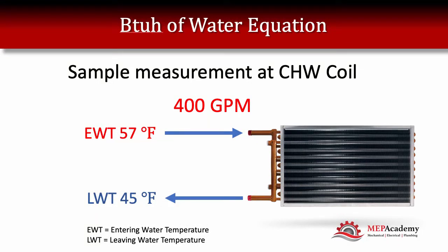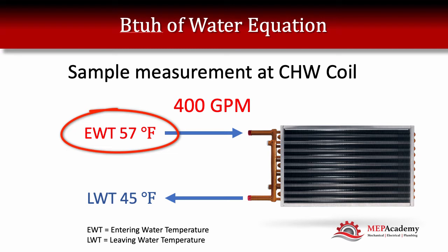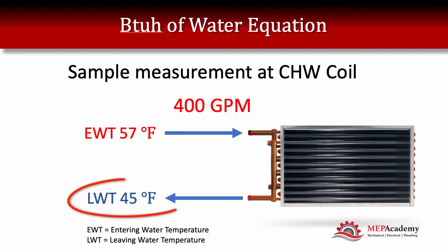For our sample here, we have a water-cooled chiller, and we've measured 400 GPM. Looking at the gauges or thermometers, we have 57 degrees entering water temperature — that would be our chilled water return coming back from the air handlers or fan coils. Our leaving water temperature gauge, our chilled water supply, shows 45 degrees — that's the water going out to the air handlers and fan coils.